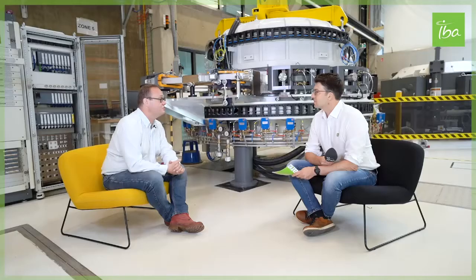Yes. A lot of our customers ask us about this. You have 560 kilowatts of beam, and the X-ray target will transform mainly, out of those 560, only 8 to 12% into X-rays. All the remaining energy, that's physics, will be heat, which will be exchanged in water. So this means we need to think about how we can reabsorb this lost energy. We just launched a program, and we have customers that ask us how they can get all this energy out of the water that is used to cool the system.